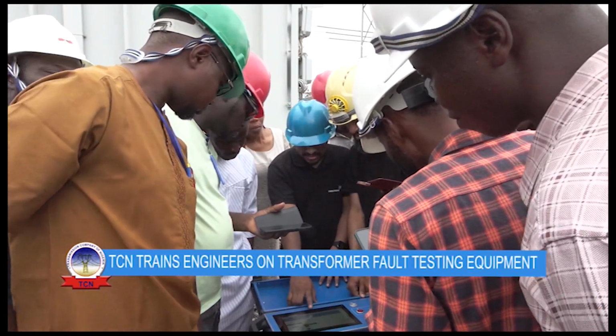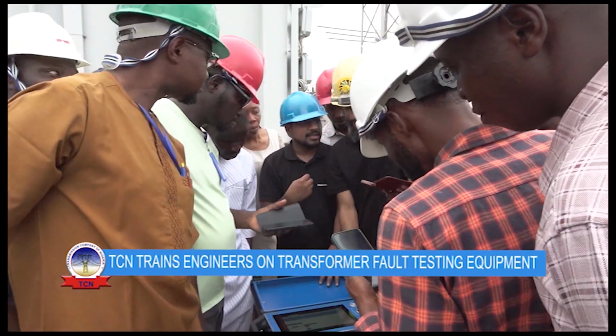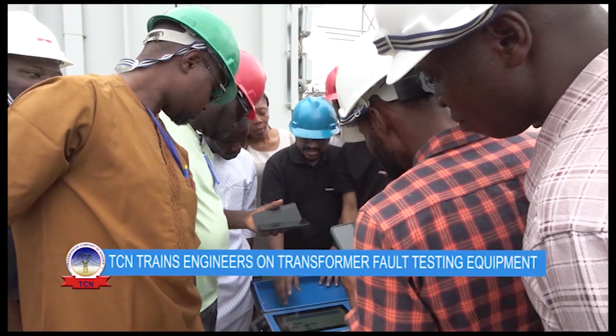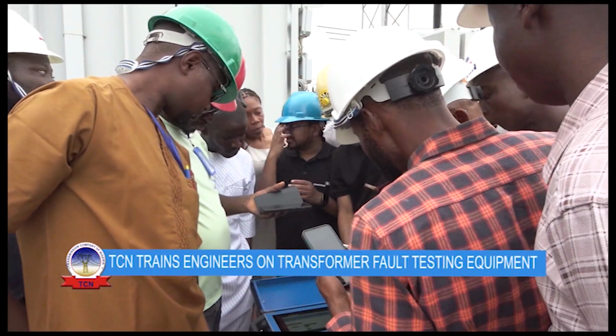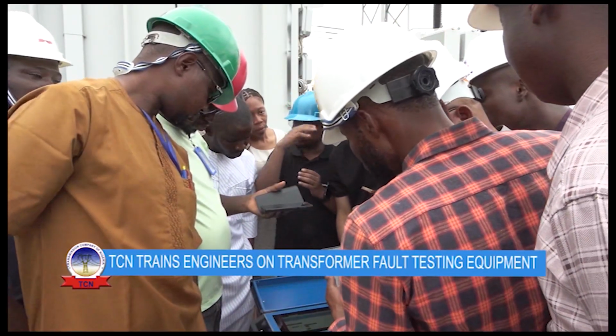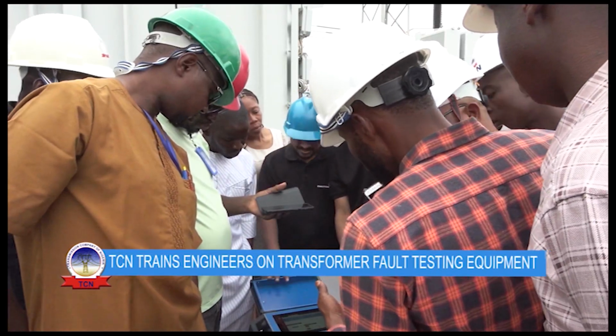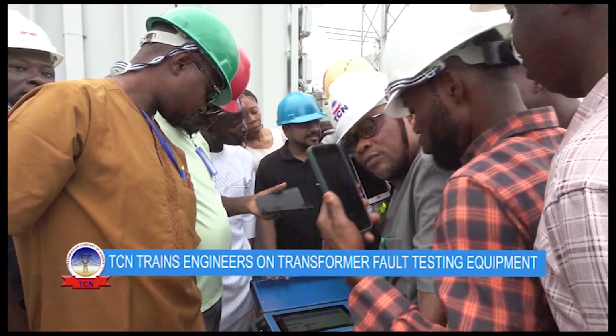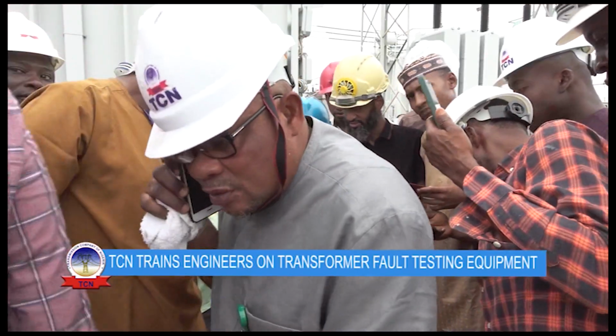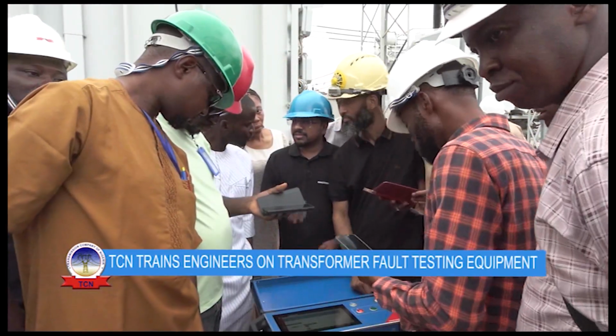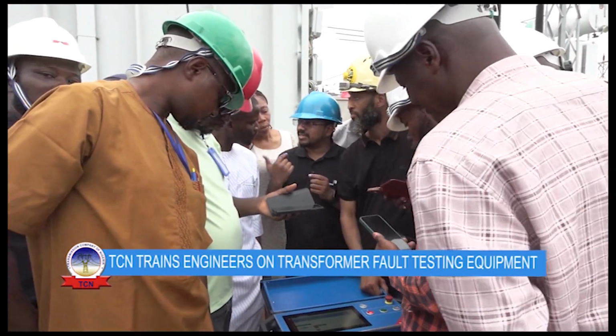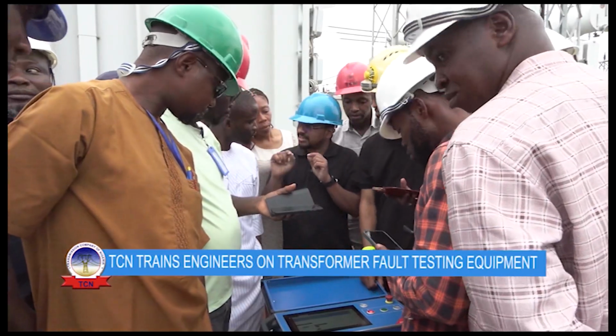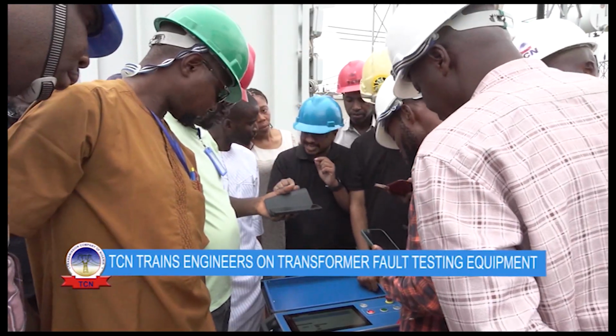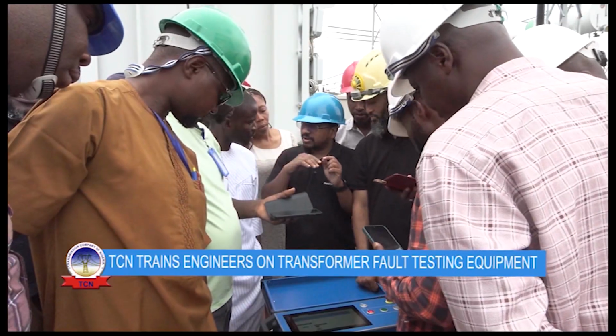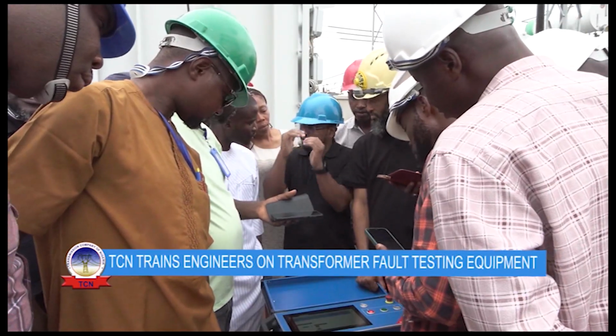R corrected is the value you have to take for the final results. R diff means the deviation in the resistance, and this deviation occurs due to the fluctuation of the current. R is the resistance. The fluctuation is because of the winding, which is an inductor. So when you inject a current into the inductor, you cannot inject directly 5 ampere or 10 ampere, because of the inductance there will be current fluctuations.